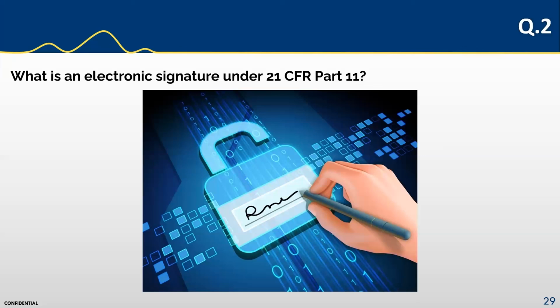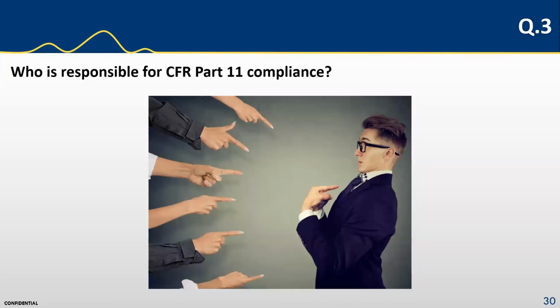With our real-time monitoring systems, for example, we tie into LDAP, and we basically will use the same electronic signature that you would use in your company, say for logging into your computer, and all that ties in neatly under Active Directory, and it's a nice closed loop. It also prevents having to put in your signatures over and over again, and everything is tied in, and you've got an audit trail as well. So it's a really nice system and tidies it all up pretty easily.